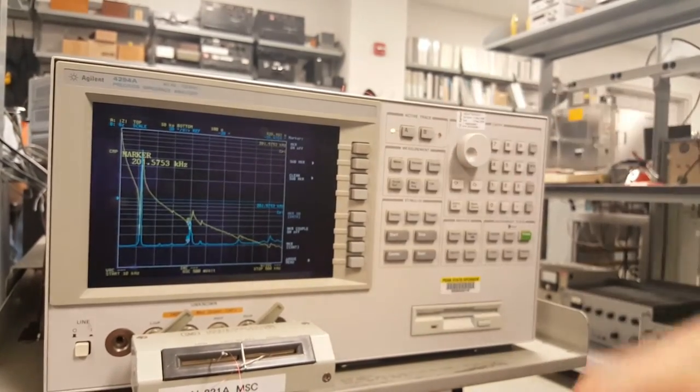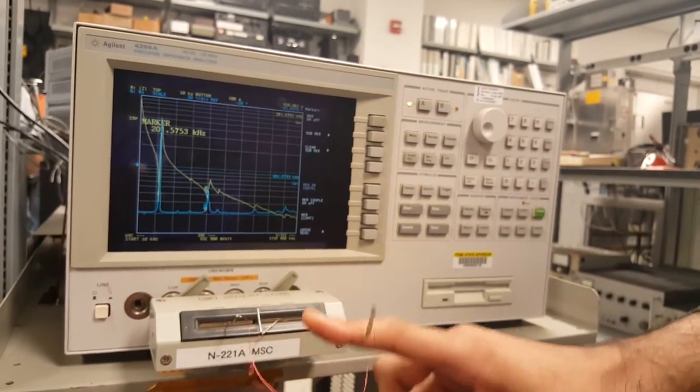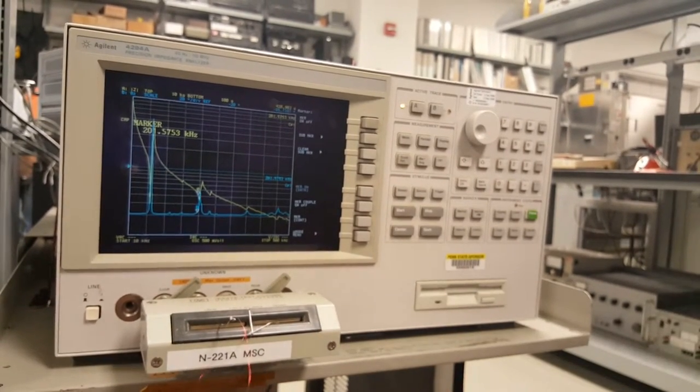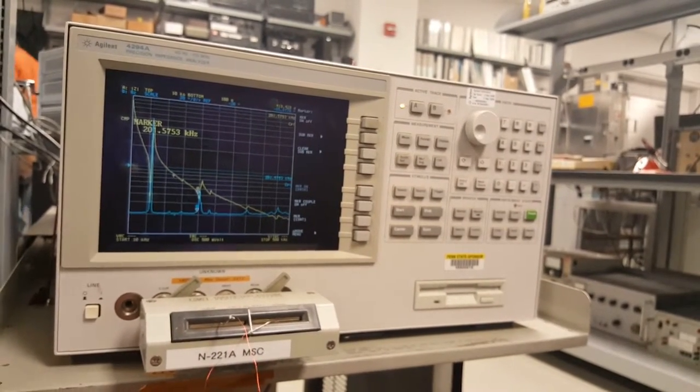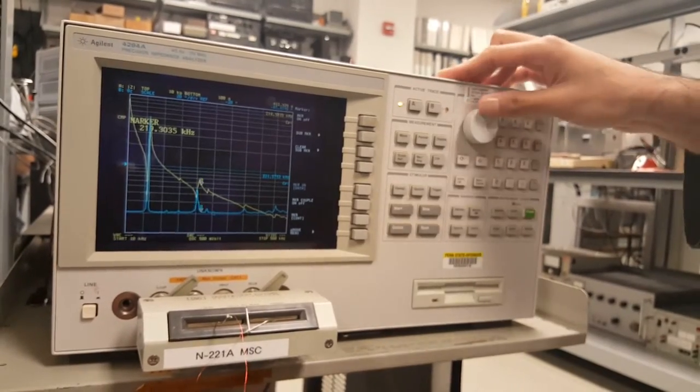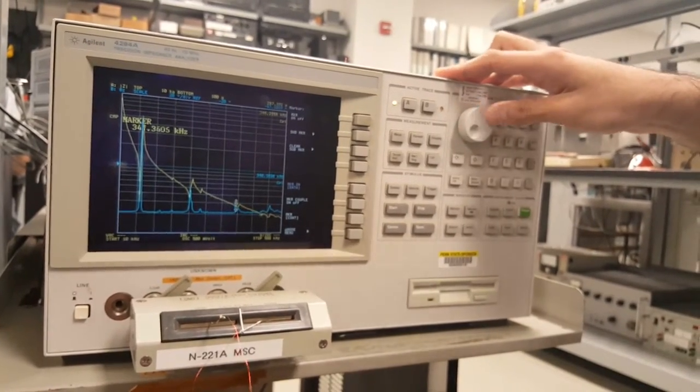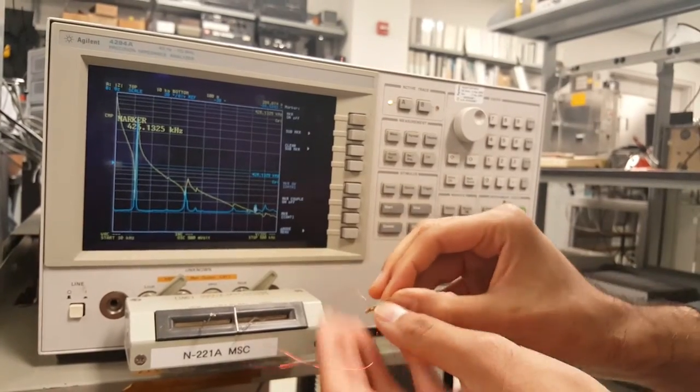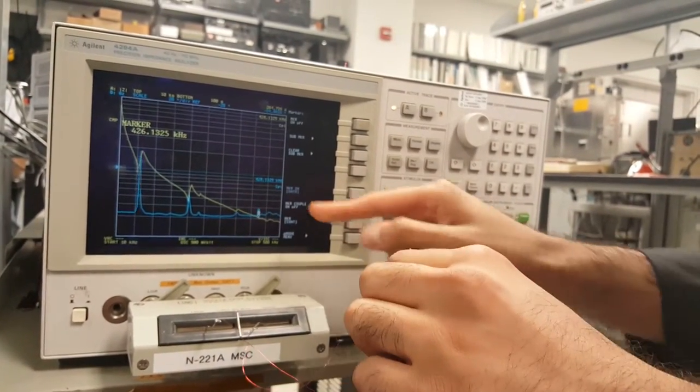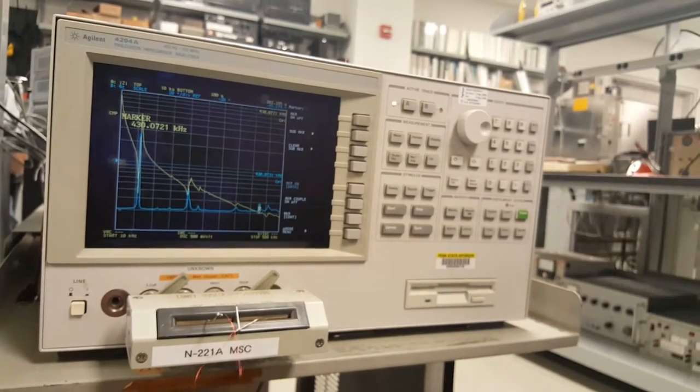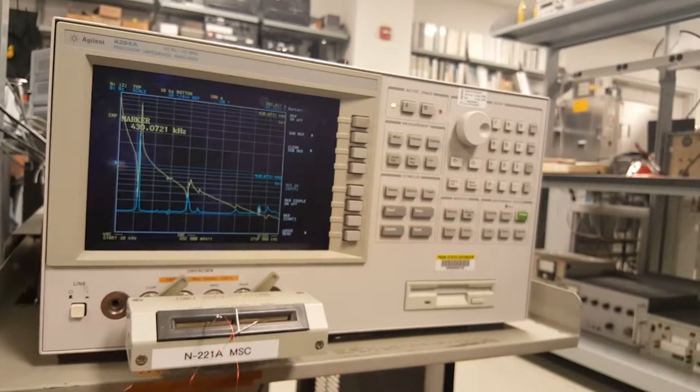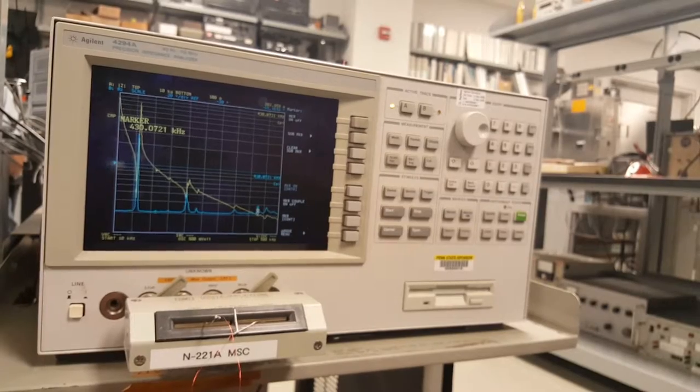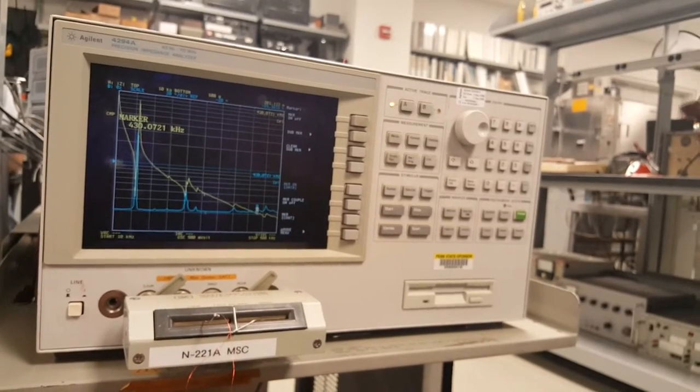Then, so this is it. We typically don't characterize the second resonance mode for this type of sample. But for the KP sample, as I mentioned in the slides, you'll have to characterize the second resonance mode frequency. You don't need the impedance or anything like that. So, and this is probably like, if you go farther up, you might find this is a thickness or something. You can calculate probably one millimeter. What's the resonance frequency of one millimeter? If it was a one millimeter length, what's the resonance frequency? Like a megahertz or 500 kilohertz or something?